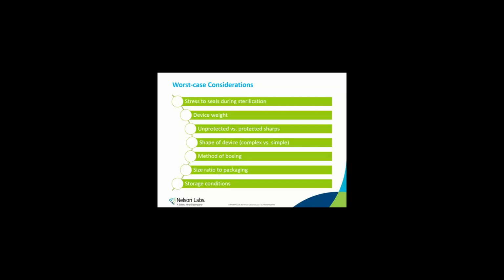Now, once you have your family, the next step, oops, a little too far. The next step is to select a worst case representative that you'll validate. As with family grouping, the rationale that you use for what's worst case will depend on what you're specifically looking at. For packaging, we look at things that present the most severe challenge to the packaging, which may or may not give us the same product if we were selecting a worst case for sterilization. Here are some items that would be worth considering when selecting a packaging worst case representative. What device in the family is able to cause the most stress to the seals during sterilization? And this relates to the vacuum pressure levels in some sterilization cycles. Which device is the heaviest?